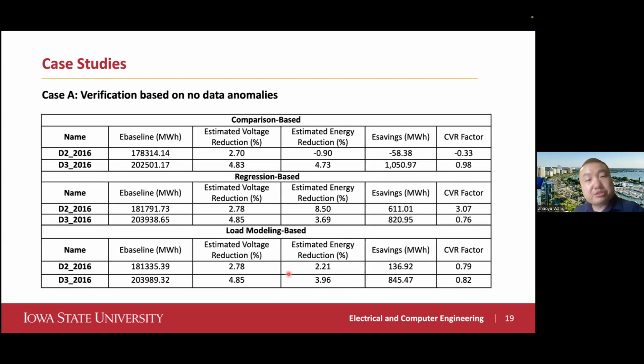Here are the results. You can see for the comparison-based method, regression method, and load modeling method, for each data set, what's the energy saving and what's the CVR factor. This is with no missing data, a complete data set. One thing you can easily observe is that for D2, the CVR factor is calculated all over the place, from negative to positive 3 to positive 0.8 or around 1.